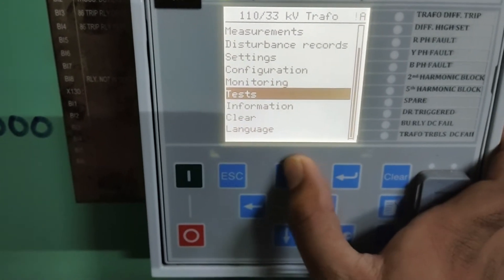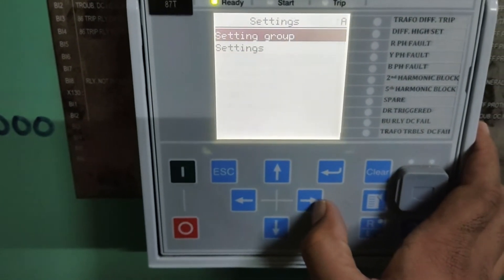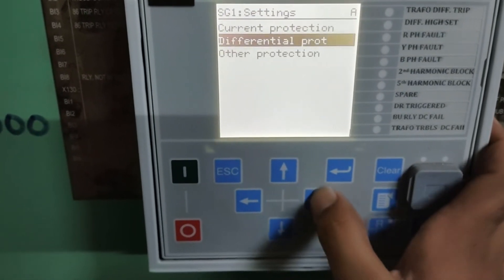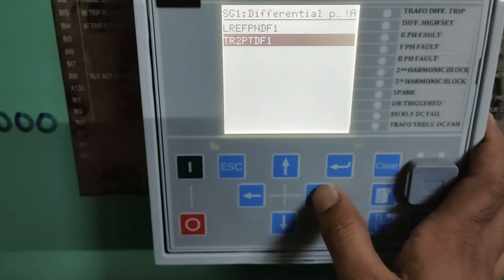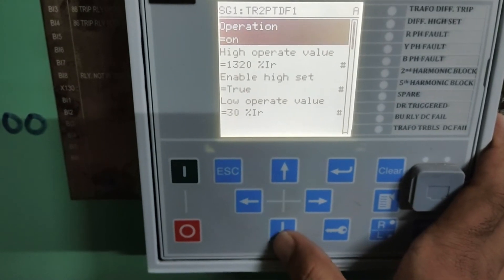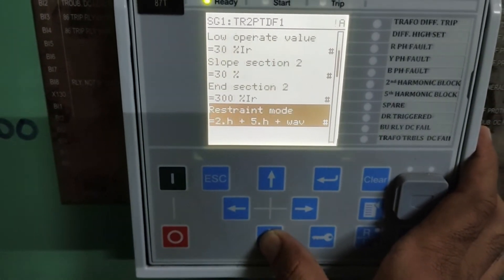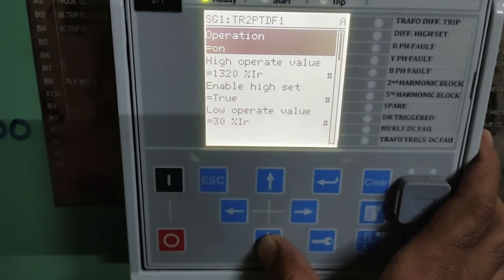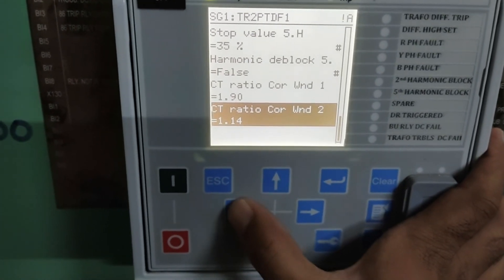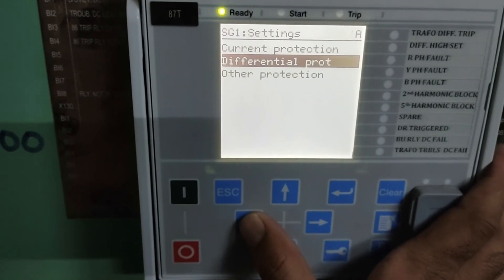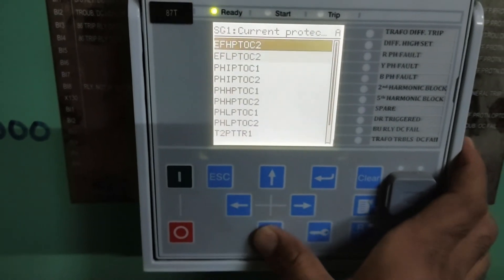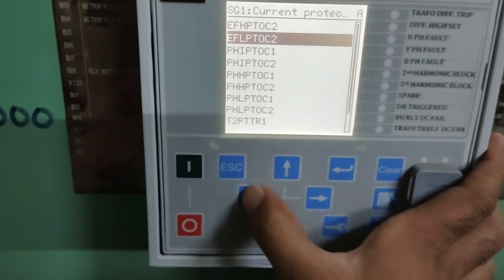If you want to read the settings, go to 'Settings' and 'View Settings'. You have to enter here and view differential protection and current protection. Mainly this relay in our substation is used for differential protection. These are the different parameters of differential protection settings — CT ratio, harmonic block 5th and others. Other current protection settings are off because we have used it as a backup relay.